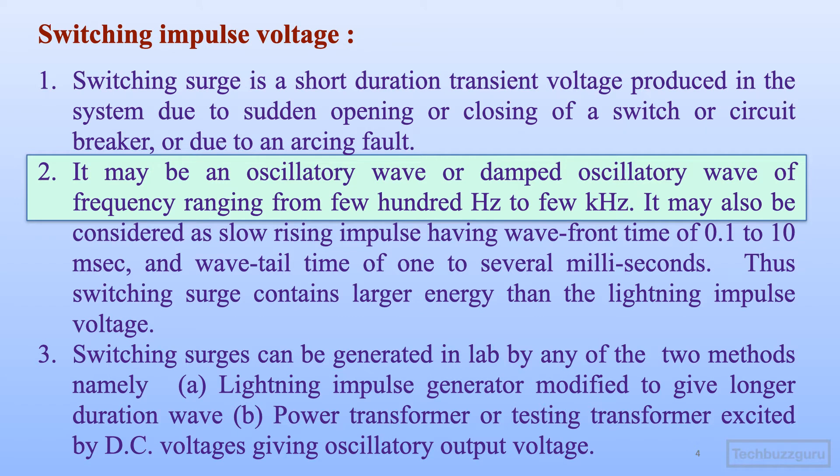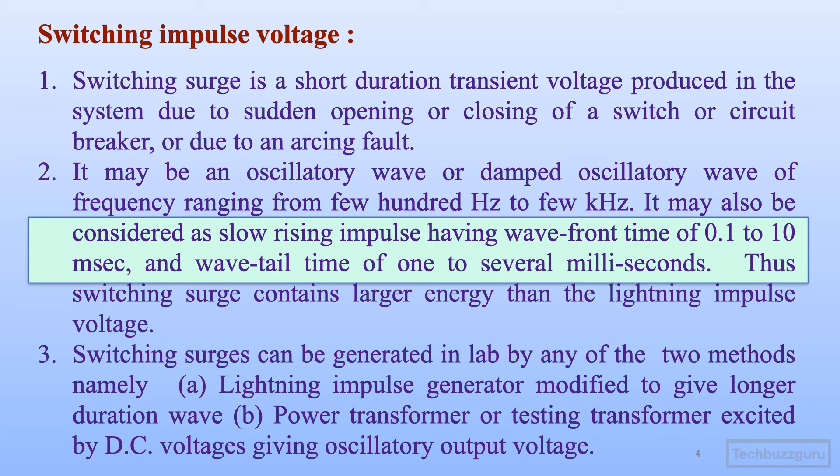These surges may be oscillatory waves or damped oscillatory waves having frequency in the range of few hundred hertz to few kilohertz. It may also be considered as a slow rising impulse wave having wavefront time of 0.1 to 10 milliseconds and wavetail time ranging from 1 to several milliseconds.